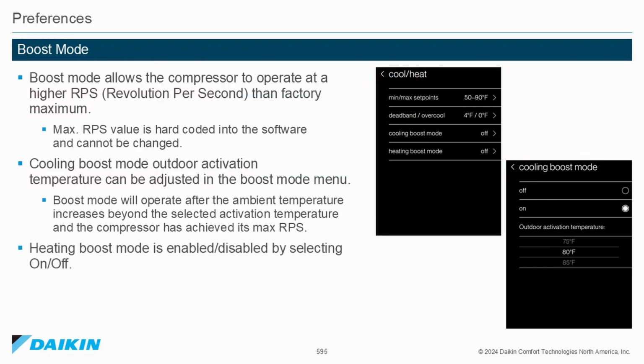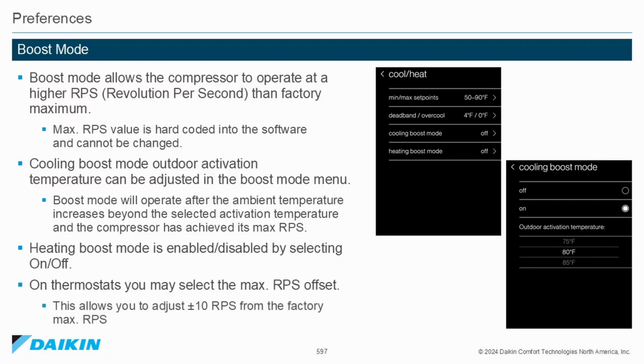Heating boost mode is enabled and disabled by selecting on or off. On thermostats, you may select the maximum RPS offset. This allows you to adjust plus or minus 10 revolutions per second from the factory maximum RPS.